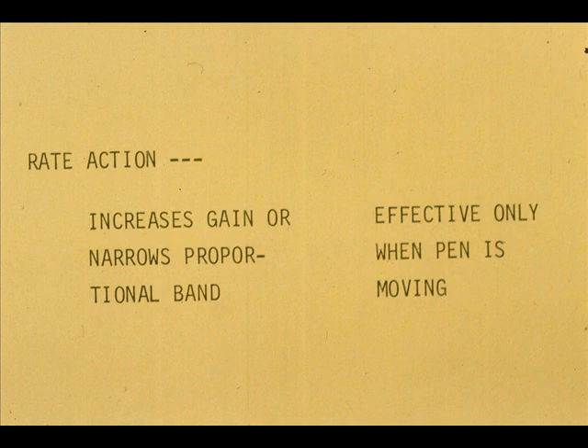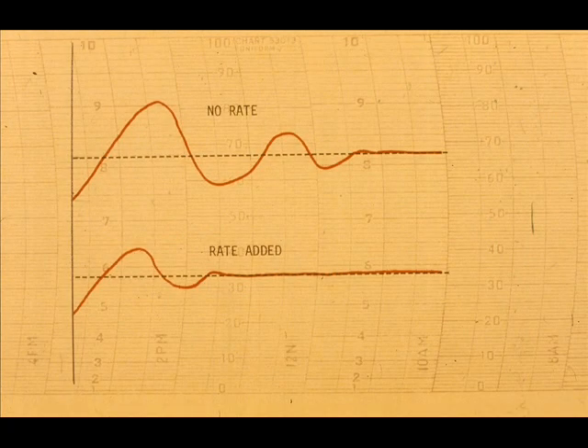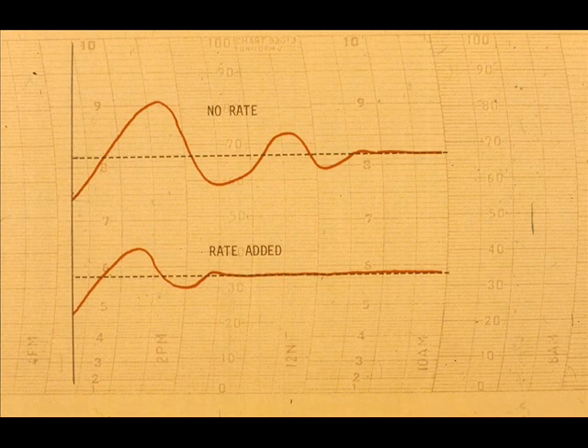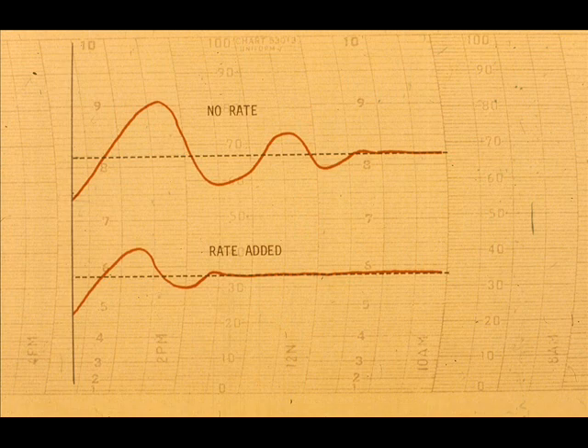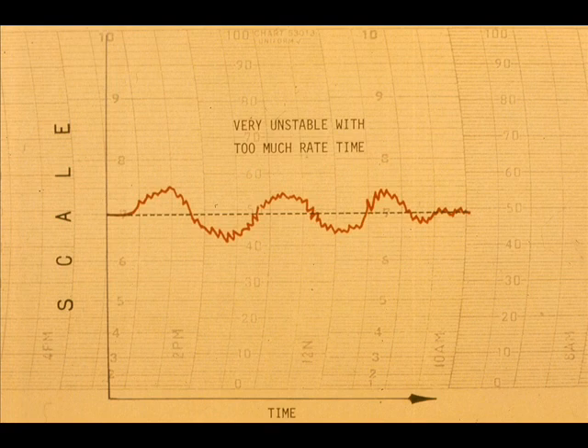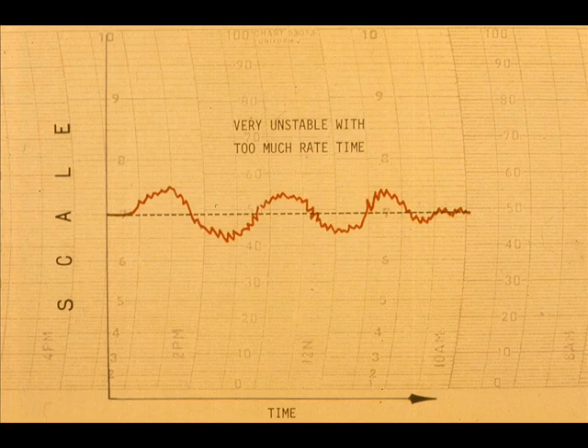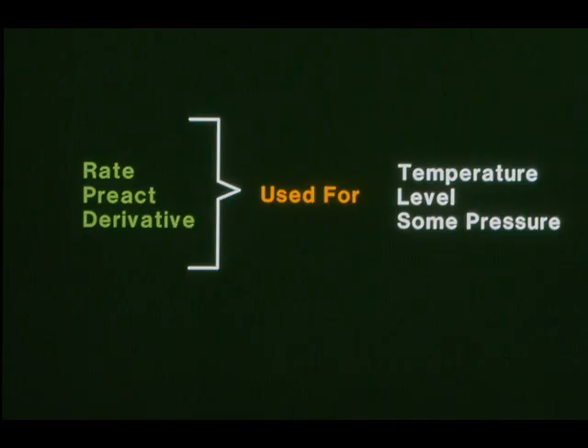Rate action increases the gain while the pen is moving. The increase is directly proportional to the rate at which the pen is moving. Where applicable and up to a certain point, the addition of rate will stabilize a control loop. But too long a rate time will make the system unstable. Rate action is applicable to temperature and level control loops, some pressures, and rarely, if ever, in a flow loop.